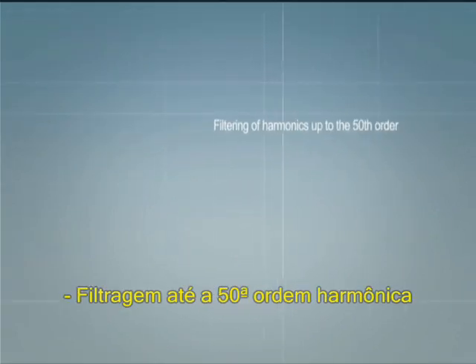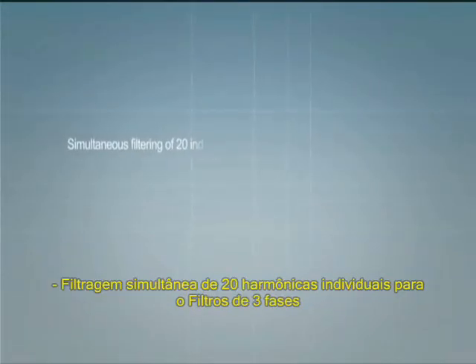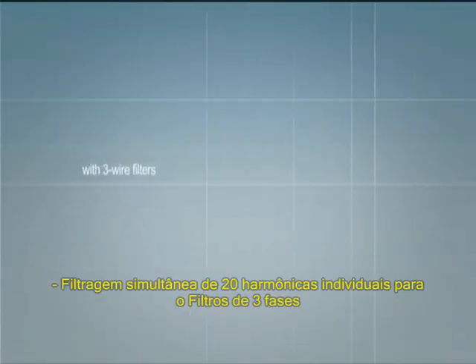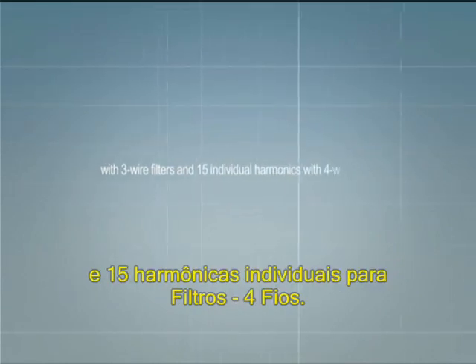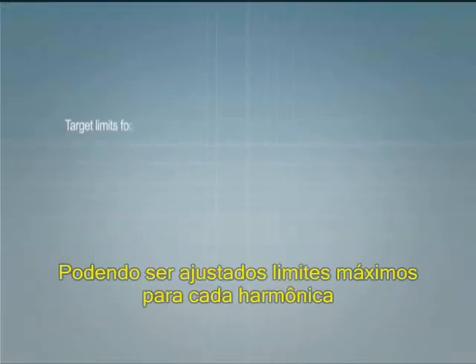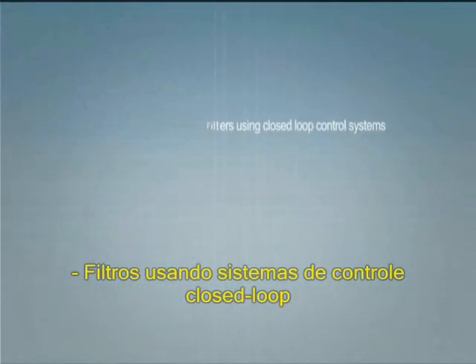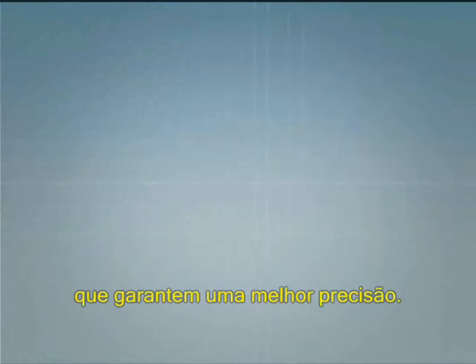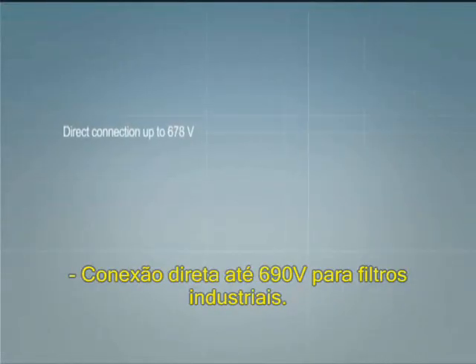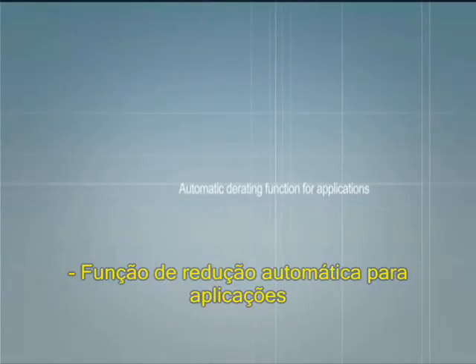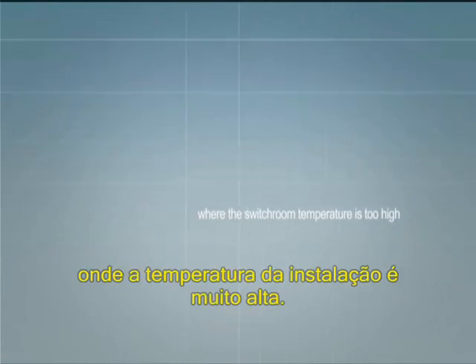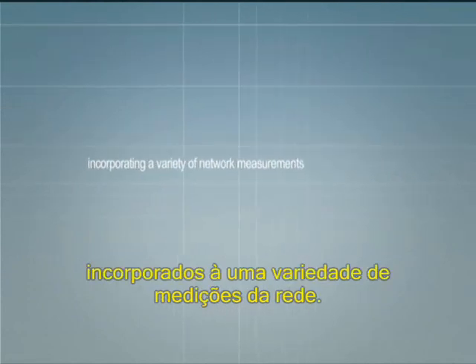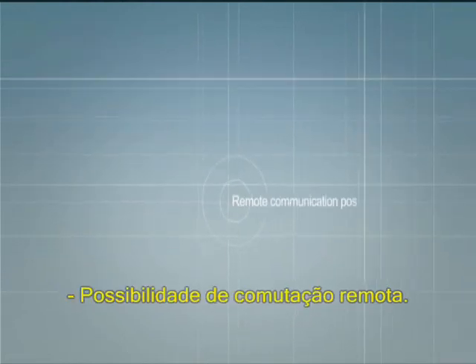Filtering of harmonics up to the 50th order. Simultaneous filtering of 20 individual harmonics with 3-wire filters and 15 individual harmonics with 4-wire filters. Target limits for each harmonic can be preset. Filters using closed-loop control systems ensuring best accuracy. Direct connection up to 690 volts for industrial filters. Automatic derating function for applications where the switch room temperature is too high. Easy-to-use graphical user interface incorporating a variety of network measurements. Remote communication possibilities.